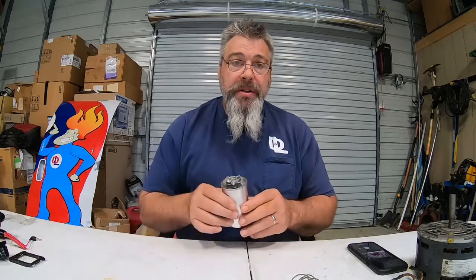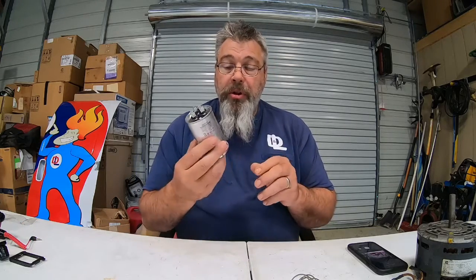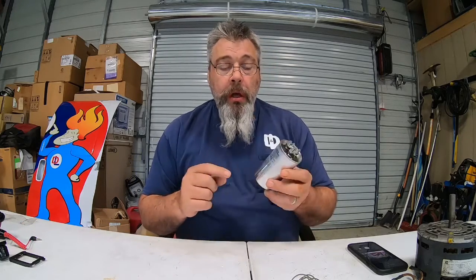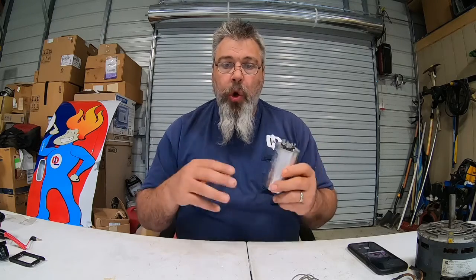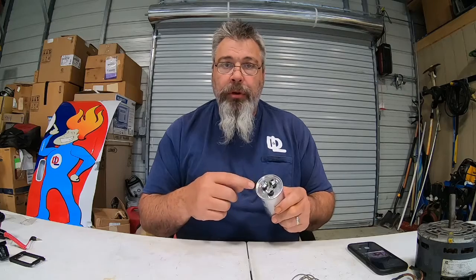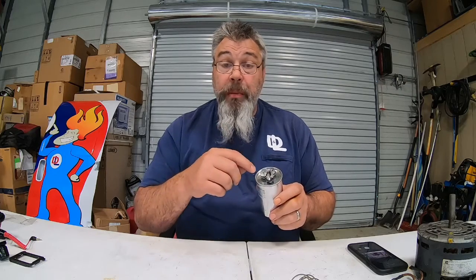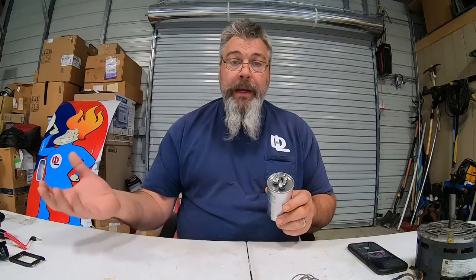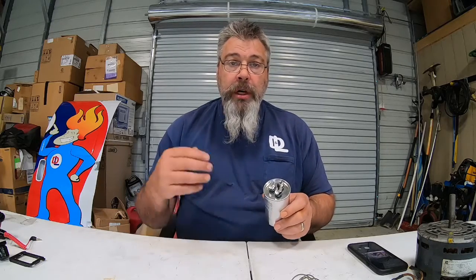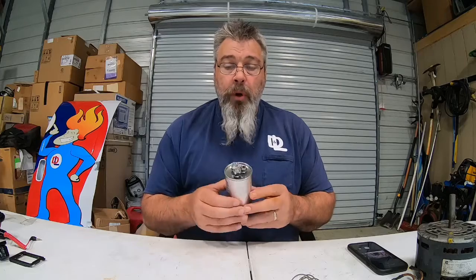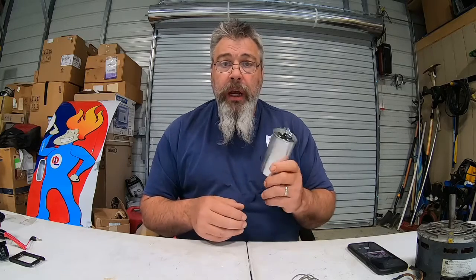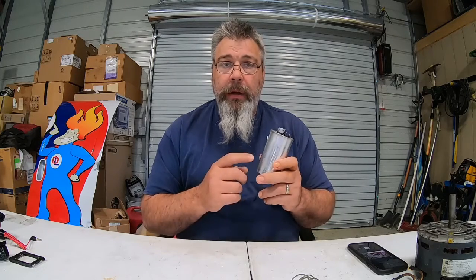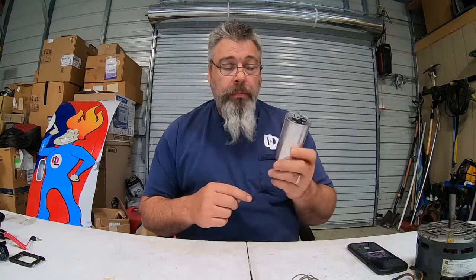One of the components that I have here on the table is a capacitor. What is a capacitor? What does it do? A capacitor is something that stores energy. It stores energy inside these terminals to make sure that when your unit starts up and your compressor and motor start up, it doesn't take the energy from your house. It doesn't dim your lights. Most common factors of a unit in the summertime going bad is a capacitor.